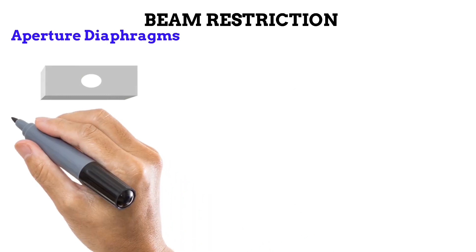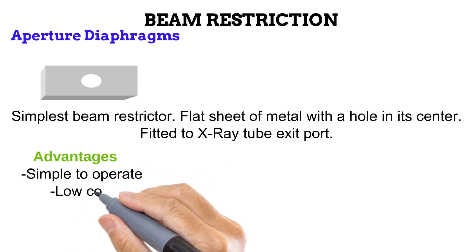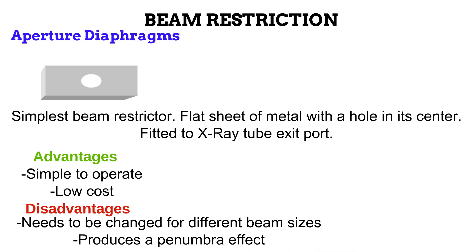First, the aperture diaphragm. This is the simplest beam restrictor on the market. It is made of a flat sheet of metal such as lead, and it has a hole in its center. It is attached to the exit port of the X-ray tube. The wide beam of photons coming from the X-ray tube will be absorbed by the lead, and it is only at the center hole of the diaphragm that photons will pass through. This means that the wide beam coming from the X-ray tube is reduced to a narrow beam by the diaphragm. The advantages are that it is not complicated to attach and detach, and that it is less expensive. However, because it cannot be adjusted, multiple aperture diaphragms need to be purchased for different intended beam sizes. Also, aperture diaphragms produce geometric unsharpness in the form of the penumbra effect.